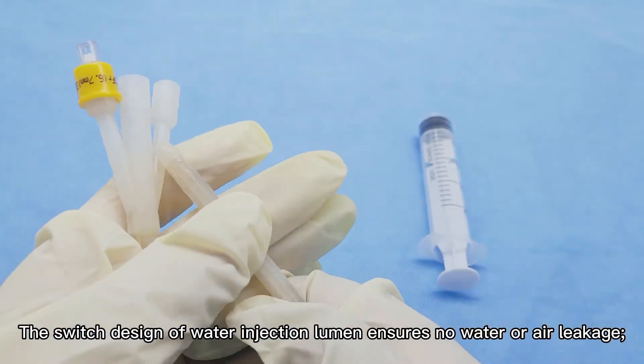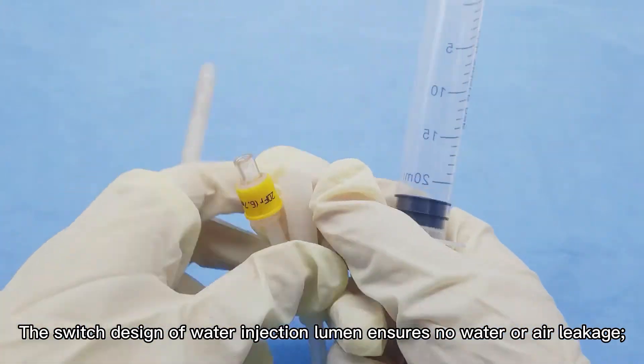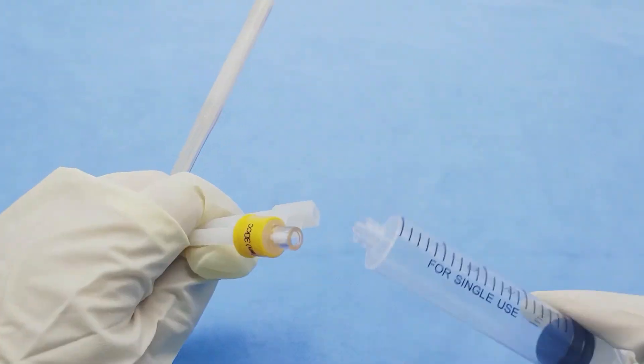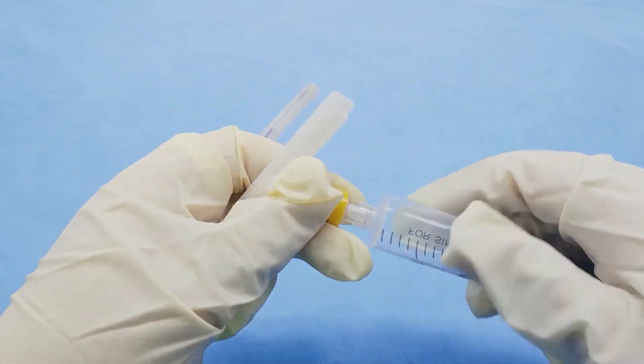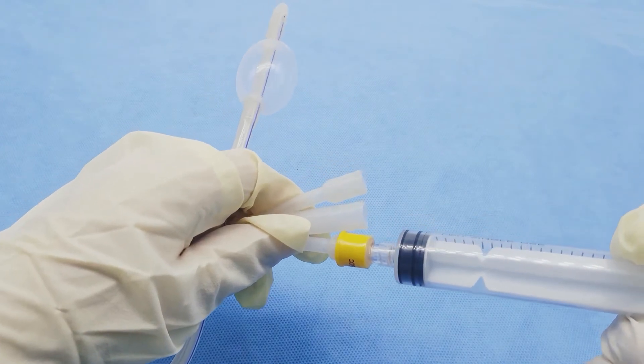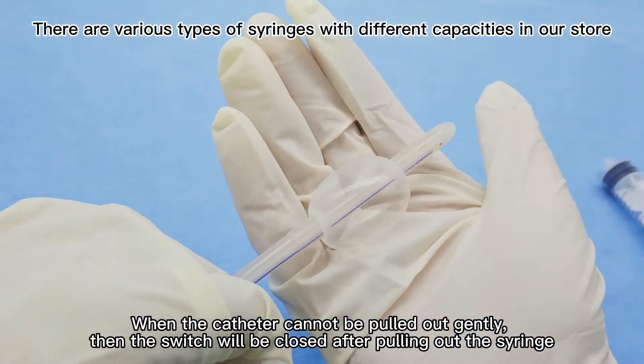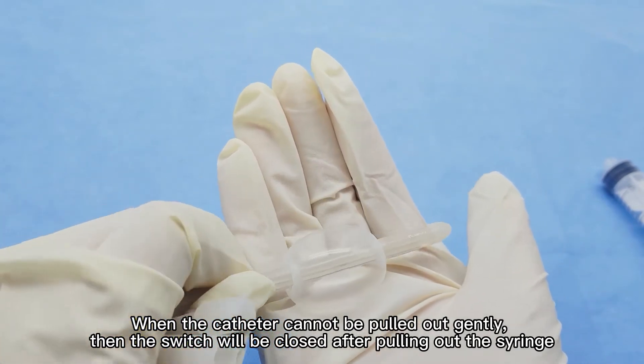The switch design of water injection lumen ensures no water or air leakage. After inserting a catheter into the urethra, inject gas or water with a syringe. After inserting the syringe, the switch of water injection lumen will open. Check balloon inflation. When the catheter cannot be pulled out gently, the switch will be closed after pulling out the syringe.